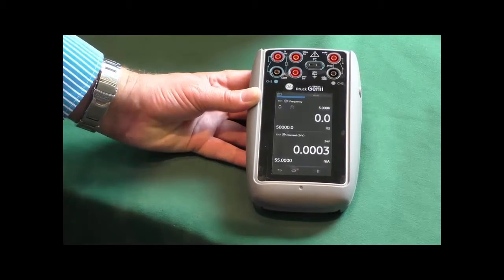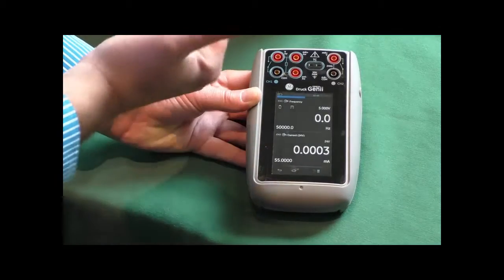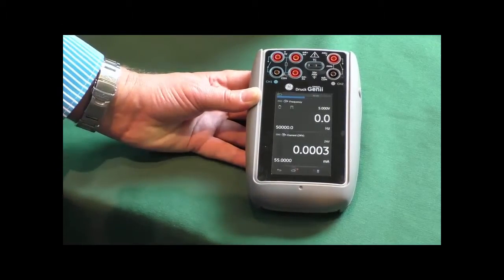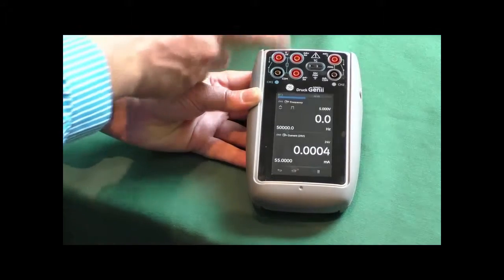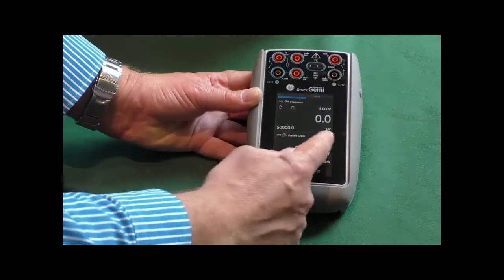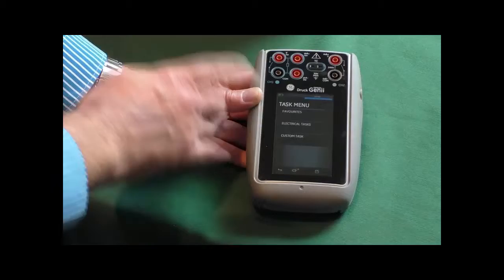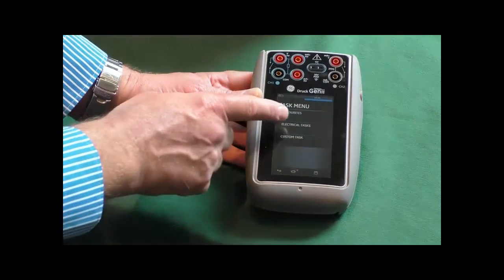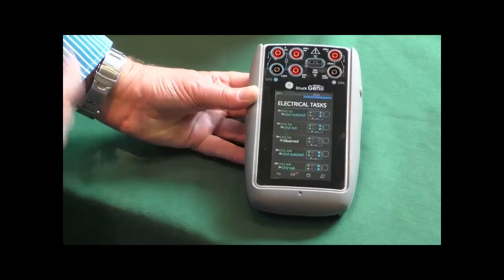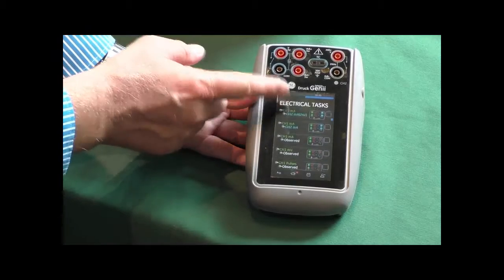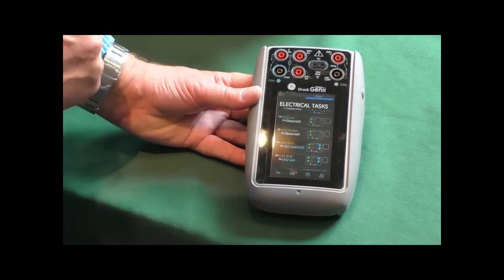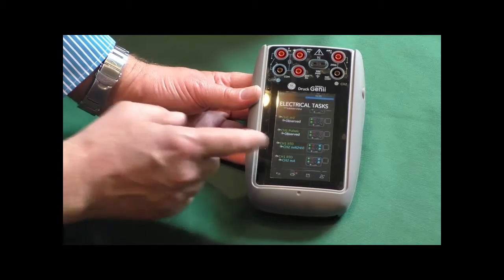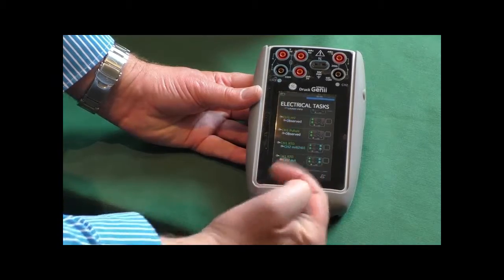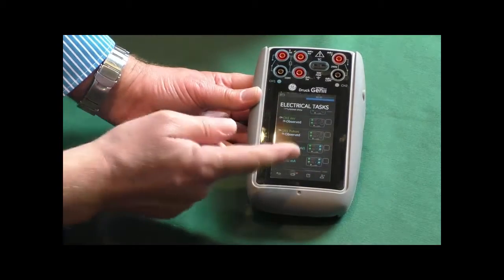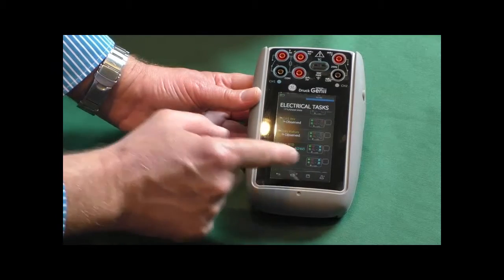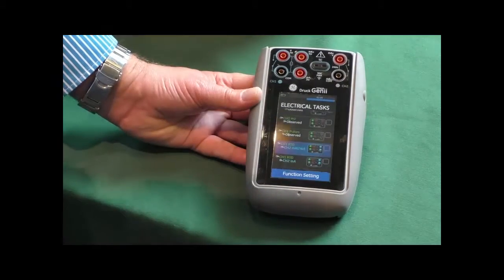So we're working with the transmitter, so what I want to do is power that transmitter from this device. So I'm going to provide 24 volts to do that. And as this transmitter's input is an RTD, I want to simulate an RTD on channel 1. Okay, so I can actually go into this manually and do what we call a custom task and set that up for each one individually. But we also have our electrical tasks set up in here to make that a lot easier for us. And if we scroll down, and what I'm looking for here is channel 1, I want an RTD, and channel 2, I want milliamps and 24 volts. The other good thing on the graphic, it shows me where I need to connect to on these two channels. So quite simply now, I will select channel 1 RTD and channel 2 24 volts and milliamps. So we just select that.